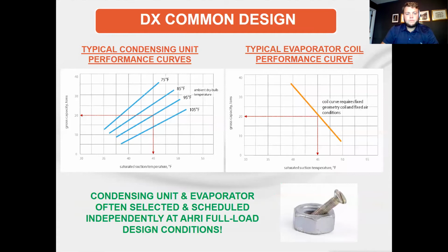So how do we cope with all these changes and still end up with a successful project? In condensing unit catalogs, you'll find curves that look like the chart on the left here. What this shows is tons on the vertical axis and saturated suction temperature on the horizontal axis. The blue lines represent, and this is probably a nominal 20-ton condensing unit, operating at various ambient conditions. 95 is the accepted design ambient in Chicago, so we'll concentrate on this.